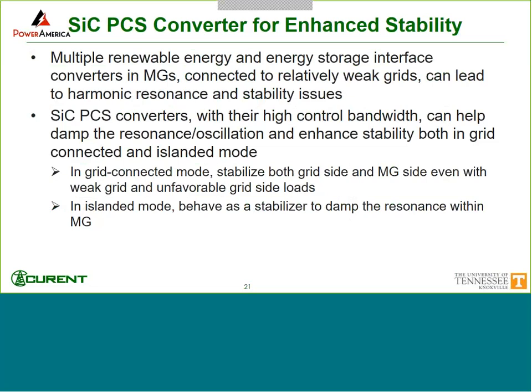For stability, we look at it in two ways, and one is to connect to the grid, right? As we know, when you connect your converter to a very strong grid, probably there would be no issue. But in some cases, you don't always have a very strong grid, and sometimes you may have loads that will exhibit unfavorable conditions. And with that, there could be small signal stability issues, like harmonic resonance. And in both islanded mode and grid connected mode, that could happen. And when that occurs, what you can do is to use control to help reformulate the equivalent impedance. But the condition for that is you would have to have enough bandwidth to do so.